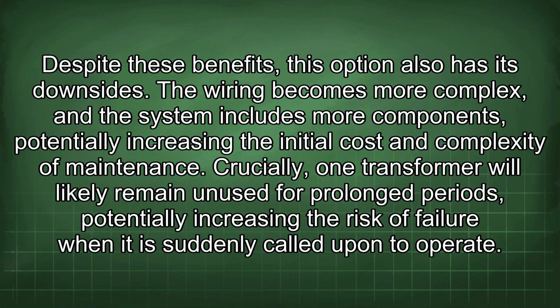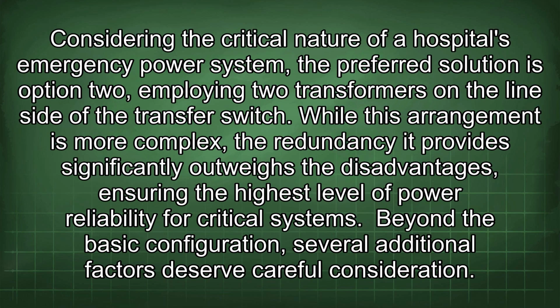Crucially, one transformer will likely remain unused for prolonged periods, potentially increasing the risk of failure when it is suddenly called upon to operate. Considering the critical nature of a hospital's emergency power system, the preferred solution is option 2, employing two transformers on the line side of the transfer switch. While this arrangement is more complex, the redundancy provided significantly outweighs the disadvantages, ensuring the highest level of power reliability for critical systems. Beyond the basic configuration, several additional factors deserve careful consideration.